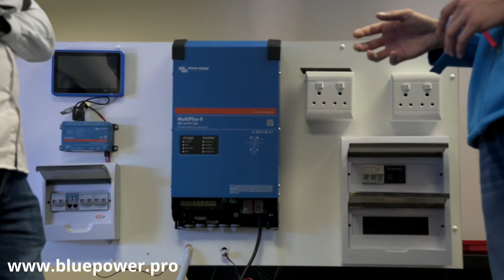According to recommendations, that varies by standards and local regulations, but Victron's recommendation is to only fuse the positive wire, because the communication bus operates on the negative wire. If that link is broken, you're going to struggle to restart the system in certain scenarios. So the recommendation is to fuse only the positive wire, since the negative is also used for the communication bus - Victron does not recommend fusing the negative as well.